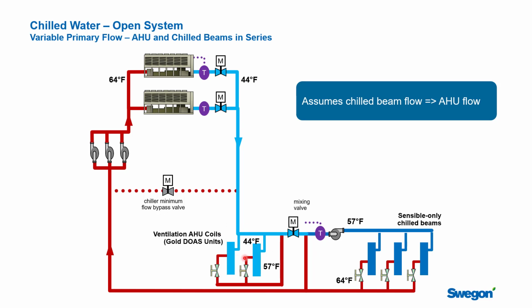Mostly that this air that we send in is actually helping with the air conditioning load. You don't have to do it this way, but most systems are designed to deliver 55 degree air to the space, and that helps with the load. It probably is going to do a third of the cooling in the zone. The other 2/3 will be picked up at the chilled water here. So you're shifting internal heat gain loads to the chilled water. Something you want to remember.